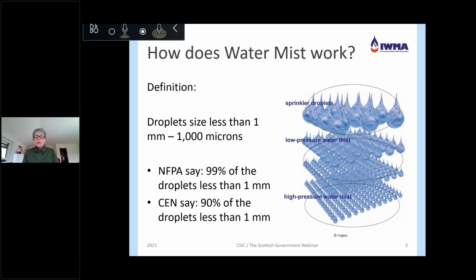During the extinguishing process, the oxygen content around the fire, and only there, drops. It nearly halves. And it is this low oxygen content that suffocates the fire. This is called the local inerting effect. Further away from the fire, the oxygen content is normal, and that means that there is enough oxygen available for humans. What I would like to add is that when water evaporates, it expands approximately 1,700 times, so 1 liter of water turns into 1.7 cubic meters of vapor. With small droplets, there is an increased surface area that will absorb heat and increase the potential evaporation. I would also like to add that there is an additional cooling effect that prevents reignition.